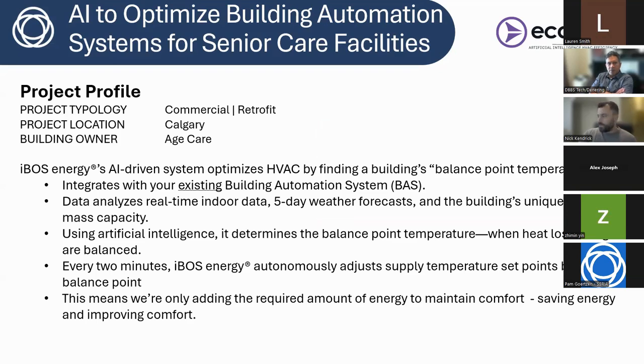To get a little bit more fine-tuned with what we're focusing on here, we're trying to establish something called a balance point temperature. I'm going to talk a little more about that in a minute, but essentially, many buildings will overheat and overcool their problems away. You add more energy, you don't have as many complaints. So what we're trying to do is find the actual need of the building at any given time and plan proactively for the future, finding that balance point. In order to achieve that, we integrate with the BAS. It goes on site. We have a little black box that plugs into the BAS. That's where all the calculations happen.